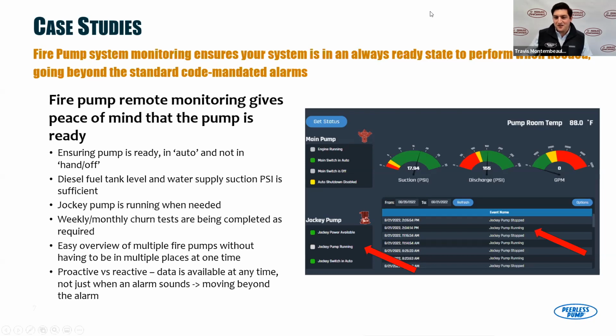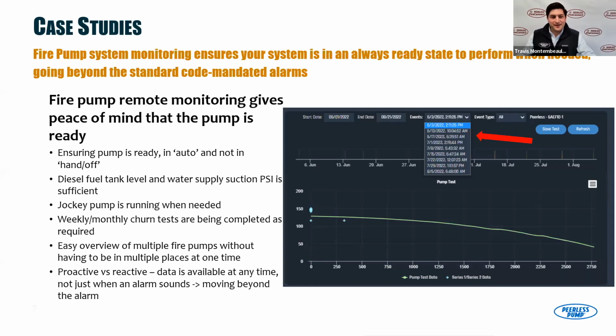You've got the event log that you can see where that arrow is, that it's turning on and turning off as it needs to. Because if that's not working, anytime you've got a pressure drop in your system, which happens over time, because we know these systems will leak over time, your fire pump would be turning on every time. And those don't turn off automatically, and usually an alarm will go out. Sometimes the fire department will show up, so you want to avoid that. So making sure that the jockey pump is ready when it needs to.